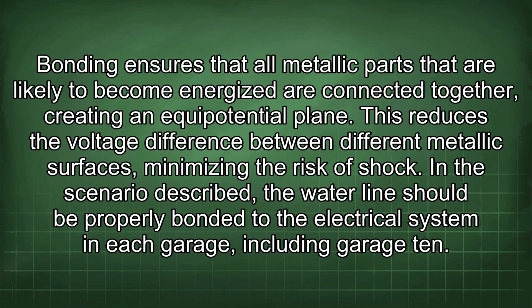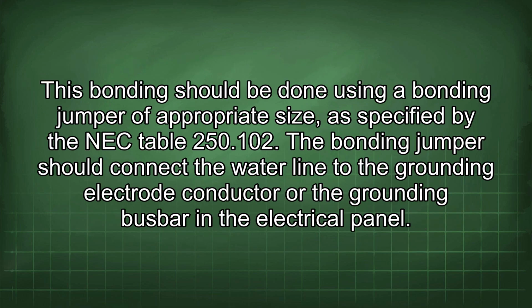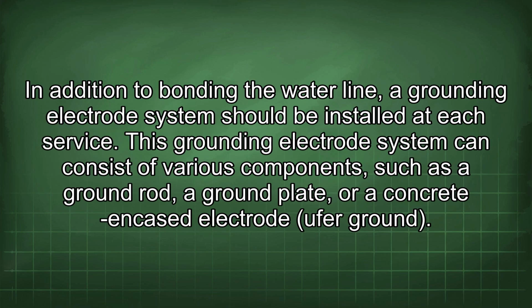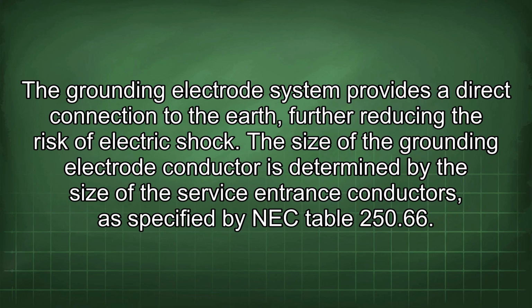In the scenario described, the water line should be properly bonded to the electrical system in each garage, including garage 10. This bonding should be done using a bonding jumper of appropriate size, as specified by the NEC Table 250.102. The bonding jumper should connect the water line to the grounding electrode conductor or the grounding busbar in the electrical panel. In addition to bonding the water line, a grounding electrode system should be installed at each service. This grounding electrode system can consist of various components such as a ground rod, a ground plate, or a concrete encased electrode, a UFER ground. The grounding electrode system provides a direct connection to the earth, further reducing the risk of electric shock.